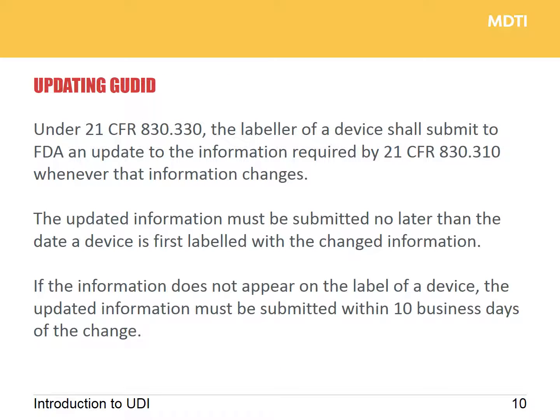One further very important point is updating the GUDID. Under 21 CFR rules, the labeler must update the GUDID when any information changes. It has to be done as soon as information goes on the label, or if the information is not on the label, within 10 days of making that business change. Please do bear these two things in mind as data starts to change within your system.